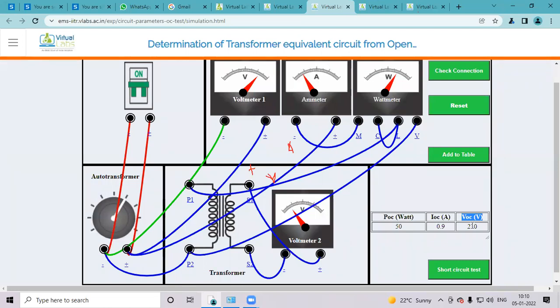Rated voltage is shown by the voltmeter. At that situation, no load current taken from the primary is 0.9 ampere, which is near about 5 to 10% of the rated current. That means if there is 10 ampere rated current, it will take about 1 ampere no load current. The no load power taken is 50 watt.